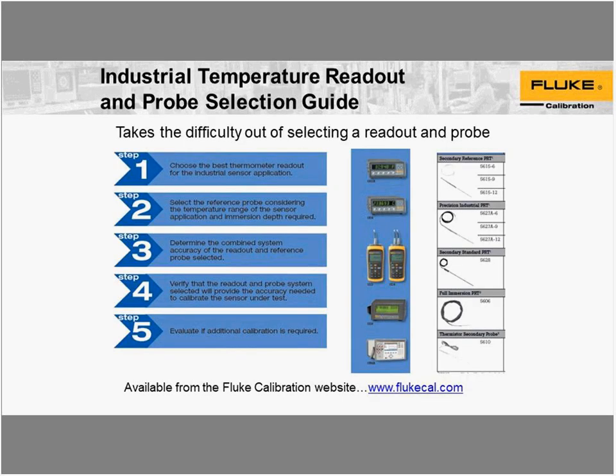All right, I'm going to explain a slide here for a second. We put together an industrial temperature readout and probe selection guide, and really what it is, as has been talked about, when you're doing a system calibration, it's important to know what the correct combinations are to use as far as readout and probe. So that's the reason we put together this guide, to give you a high-level reference of the different Fluke products, the readouts and the probes, and combining those together, what would be the total accuracy that you could see. The reference is available on our website. If you're interested in that, just go to our website and you can download that reference.